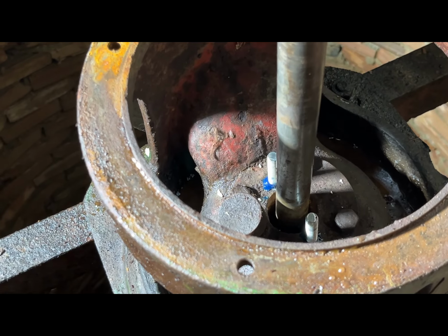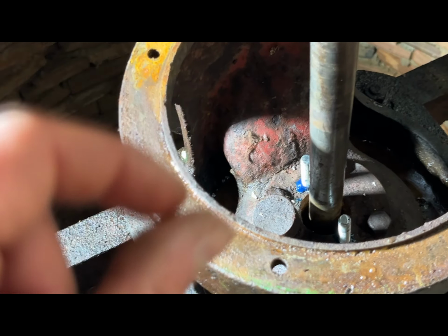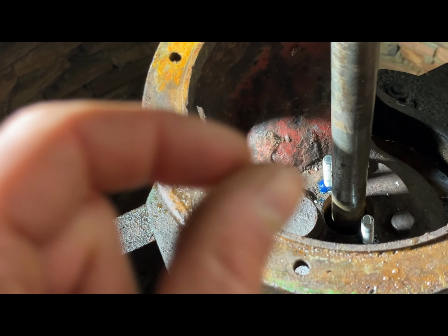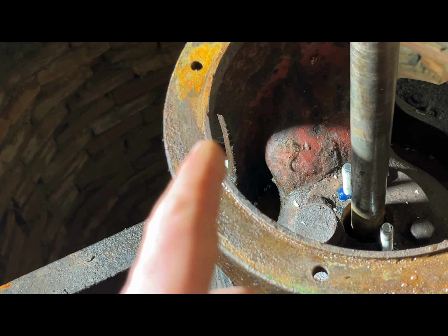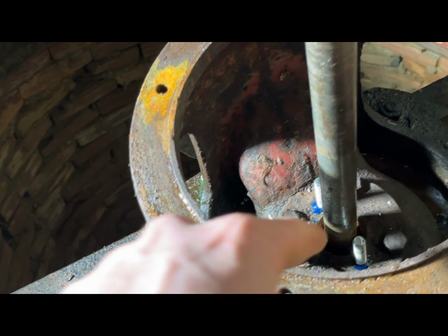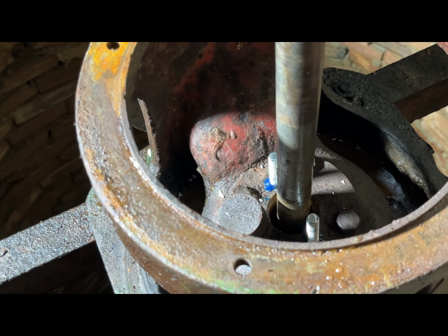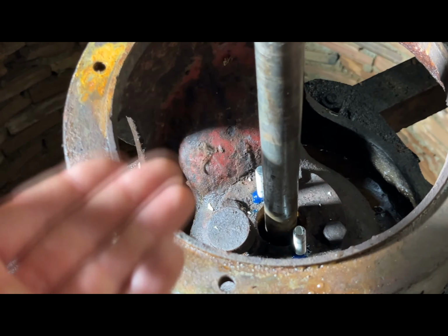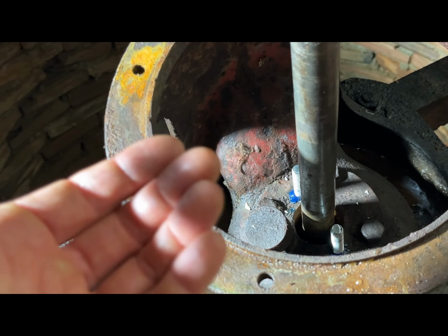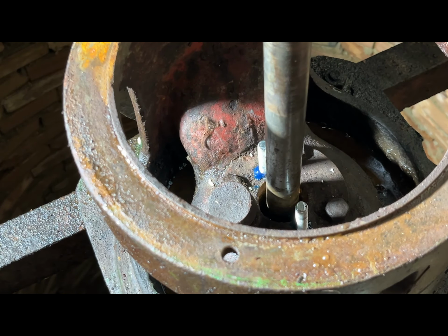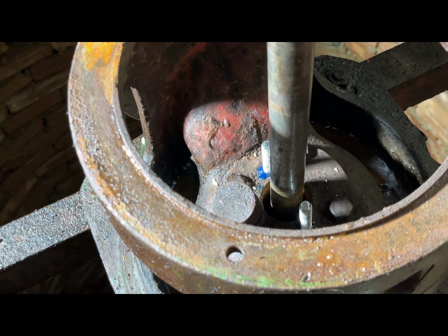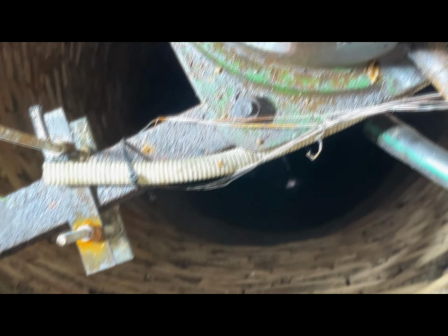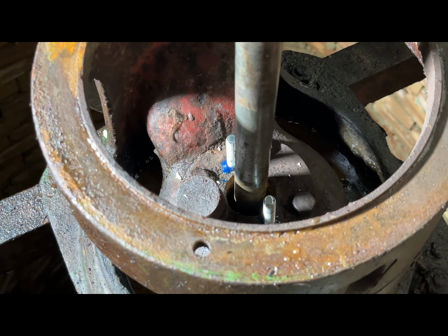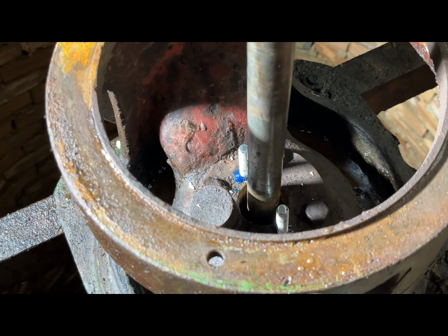You do this until the part of the gland that goes in can sit approximately 3 to 5 millimeters inside the bore. You want it not above the bore, but kind of inside it. I won't film this because the risk is very high for my camera to fall into the well, which is 20 meters deep, and I don't want to risk it, but I will show you the result.